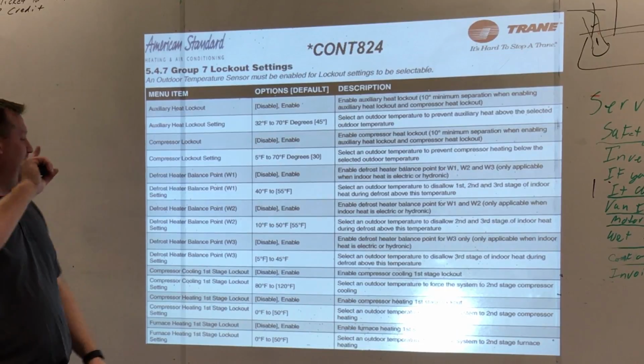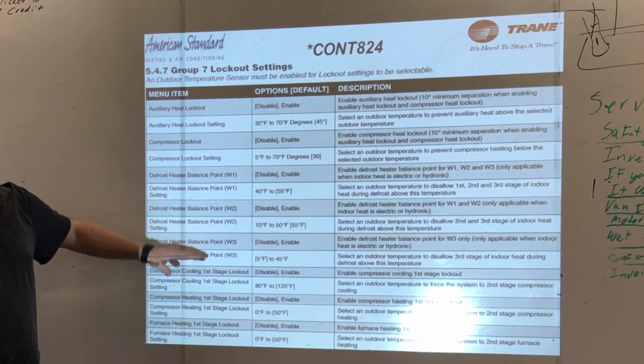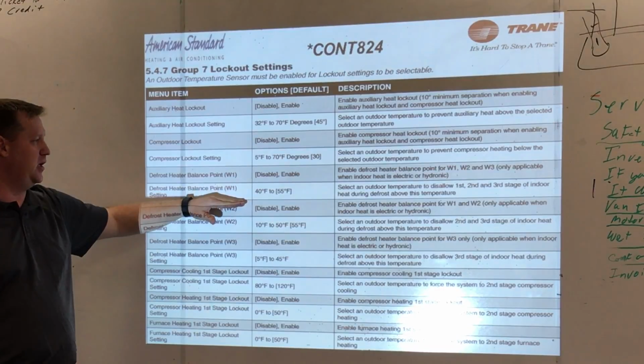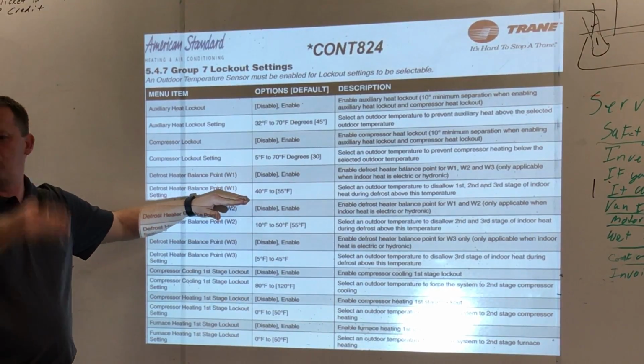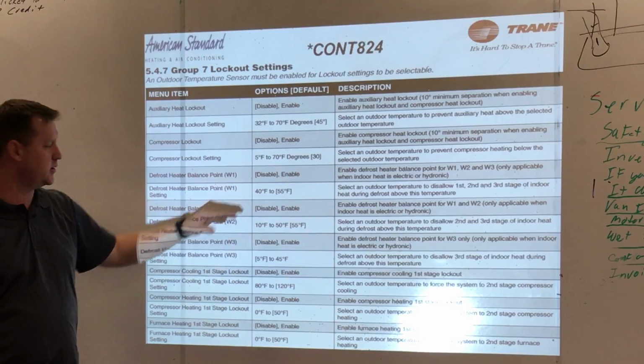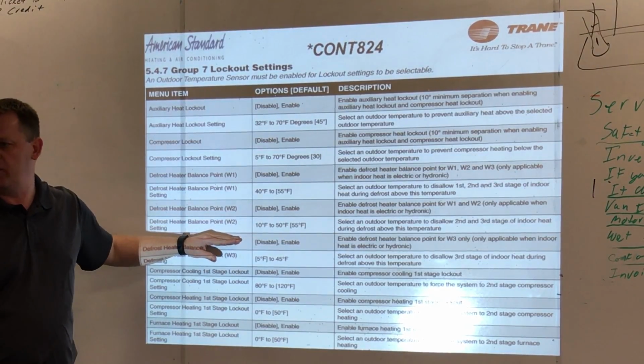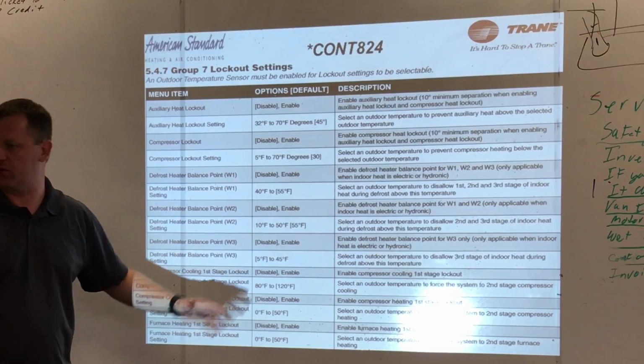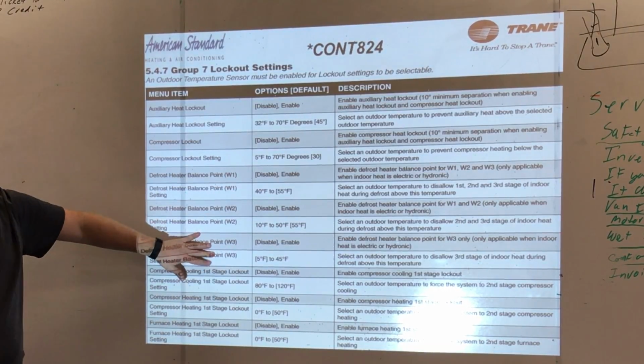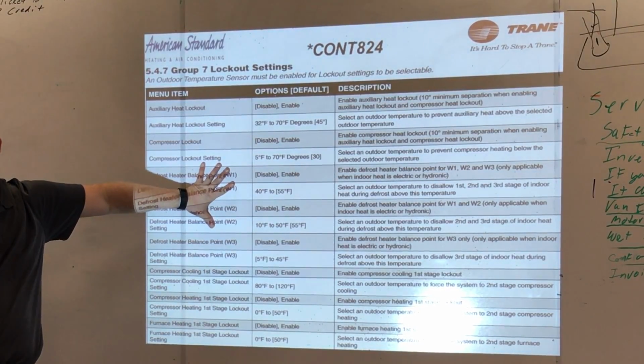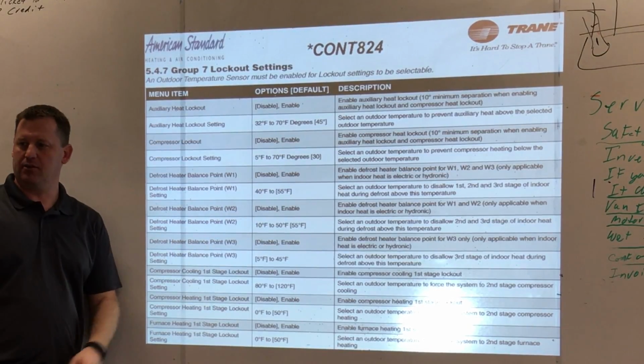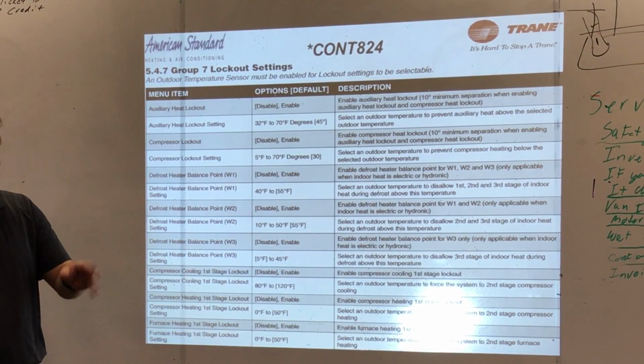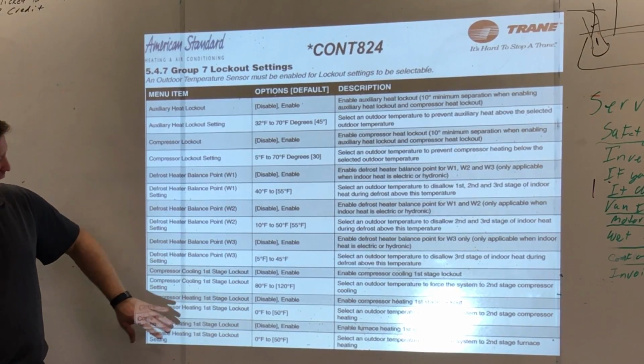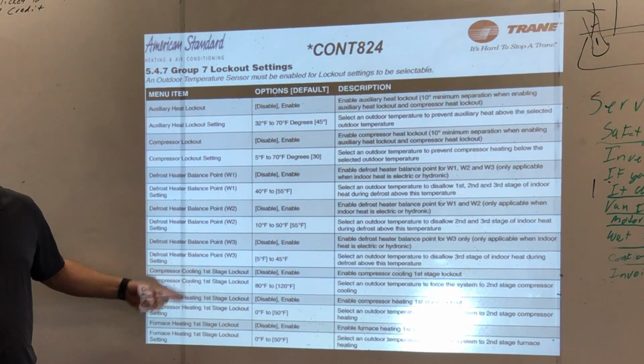And there's your bonus. Anyway, that's what those are. It's basically saying, don't allow auxiliary heat, W1, to turn on until this outdoor temp during defrost. Don't allow W2 to kick on during defrost until this outdoor temp. Same with W3. That's what all of this is. Realistically, guys, you will almost never use this, but you might have that engineer from the site who's going to kill you. Sometimes those guys are better sent to the competition. I'm just kidding. Sometimes. Anyway, this is something you might end up using.